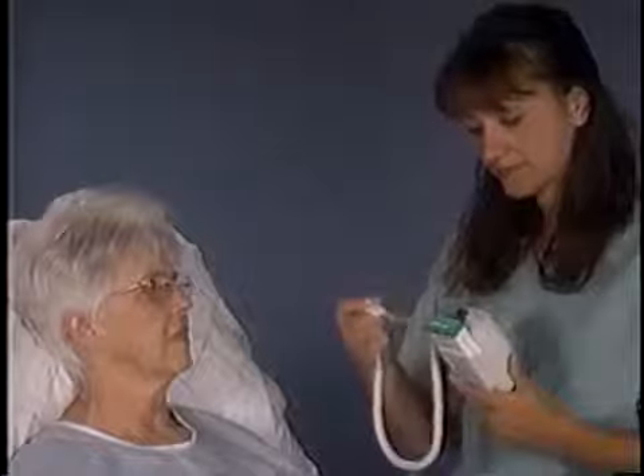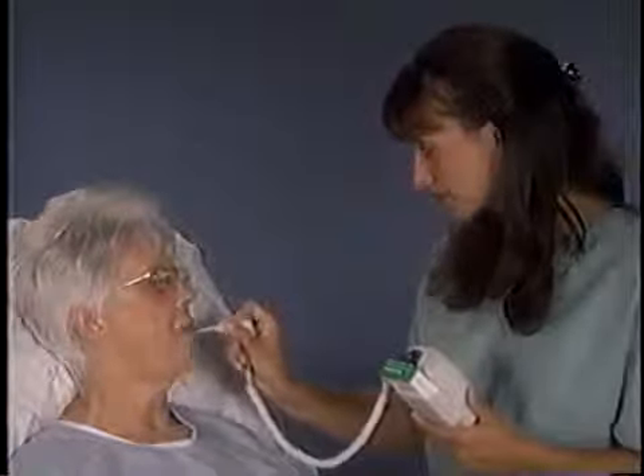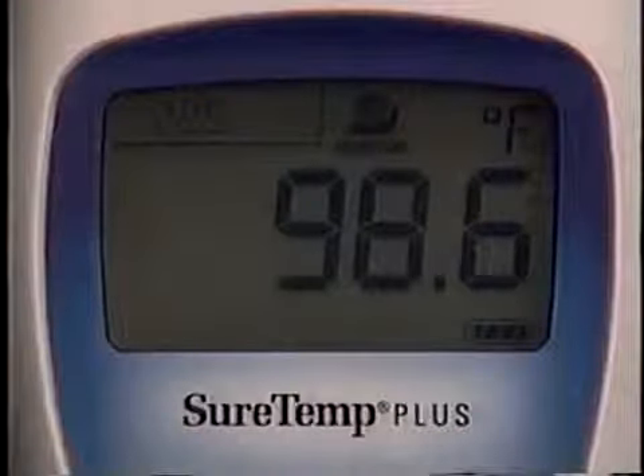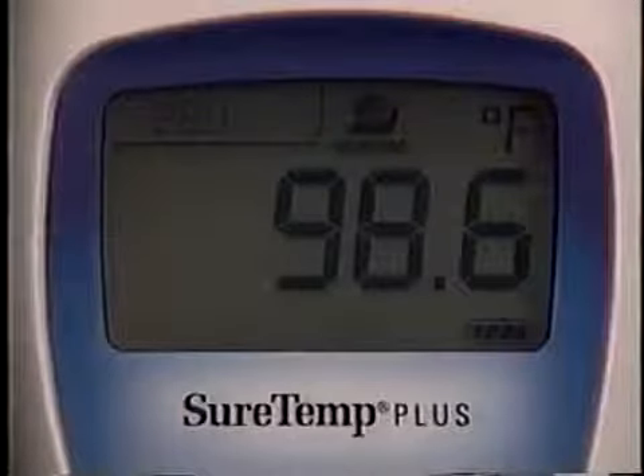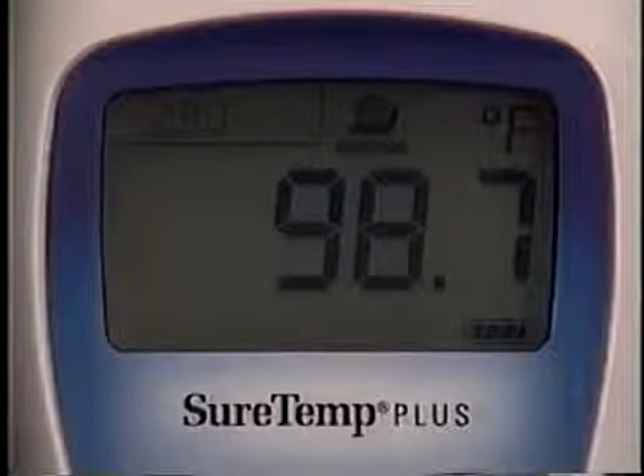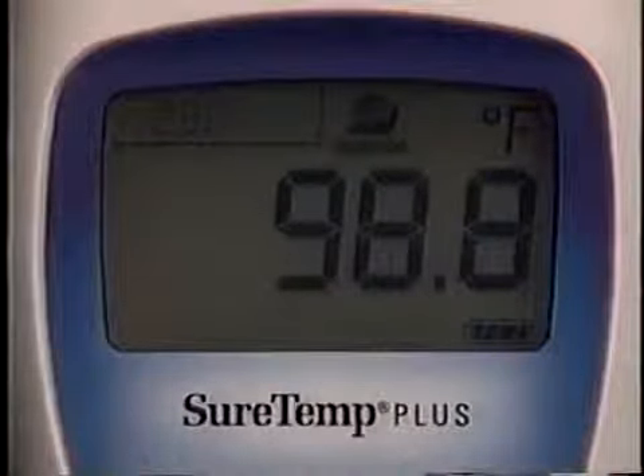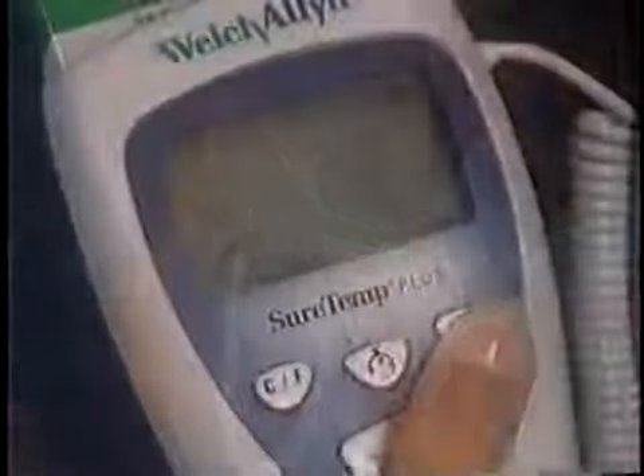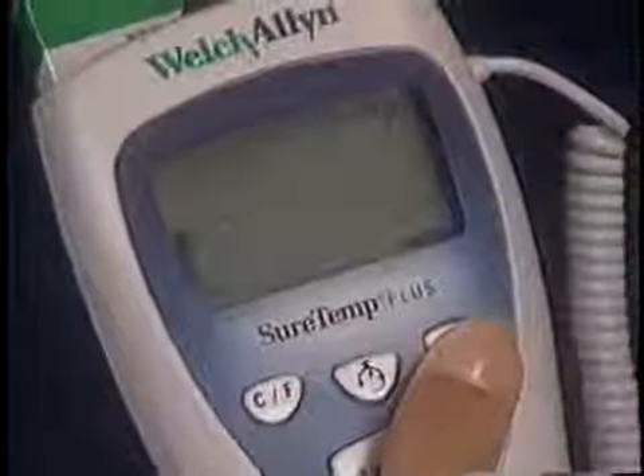Most of the temperatures you take will be in predictive mode. However, you may sometimes have difficulty getting a reading. If so, use monitor mode, which measures and displays the temperature for as long as the probe remains in place. Monitor mode measurement begins the same way as predictive mode. Use the correct probe and probe well, blue for oral and axillary temperatures, red for rectal. Insert the probe into a Welch Allyn probe cover and select the desired mode.